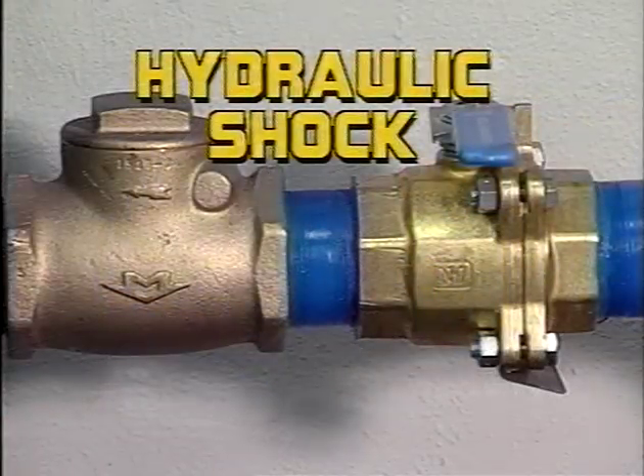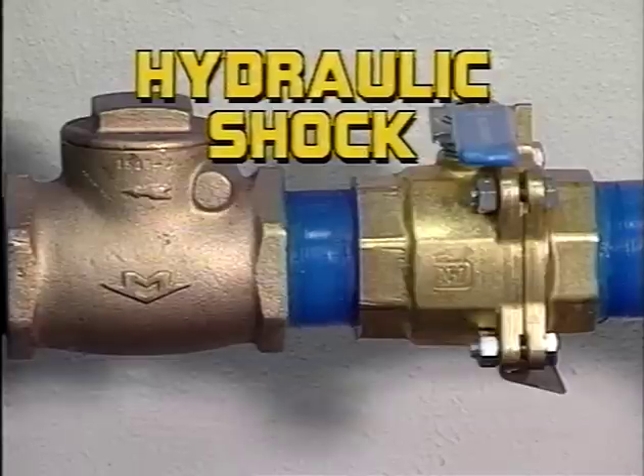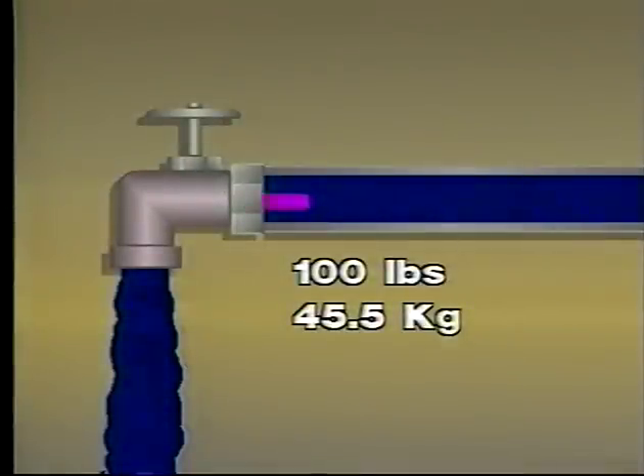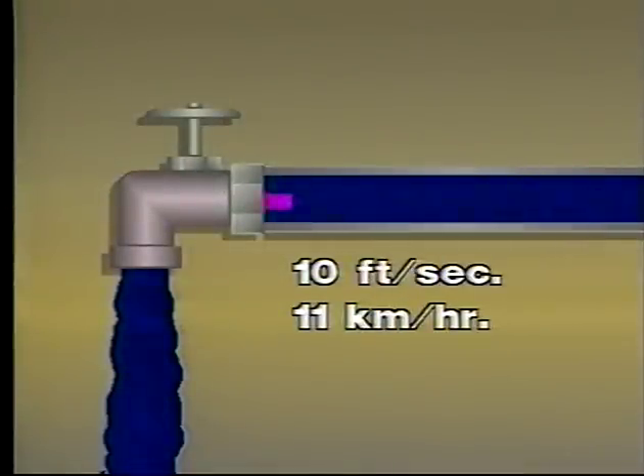Hydraulic shock occurs when a valve is closed too abruptly. When a water valve is open, a solid column of water moves from its source at the main to the valve outlet. This could be 100 pounds of water flowing at 10 feet per second or about 7 miles per hour.